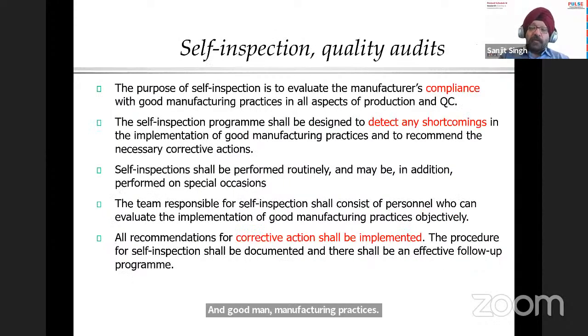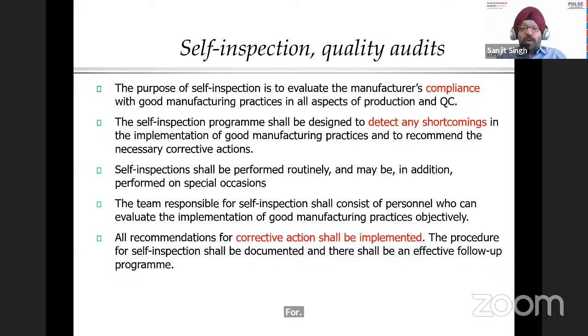Just like the old provision, there's a provision on self-inspection or self-audits or quality audits. The purpose is to evaluate the manufacturer's compliance with good manufacturing practices and also to detect any shortcomings in the implementation. So these self-inspections should be performed routinely, annually, and also based on special occasions. The special occasions can be when you receive a large complaint, you have large defects in your manufacturing, or any other areas where you have audits from a regulator or an audit from a customer.